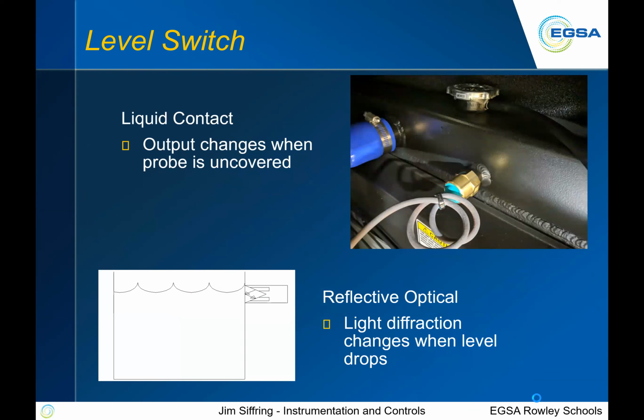Level switches, liquid contact type device. On the upper right-hand corner, you'll see a contact switch. It's just sitting there saying, if I see coolant, I'm okay. If I don't see coolant, I change state. That's a super common device. I think that's off a John Deere engine I took this shot on. Basically, when it sees fluid, it changes state. If for some reason the level goes below that, then it'll give you some indication out. Typically it'll open.